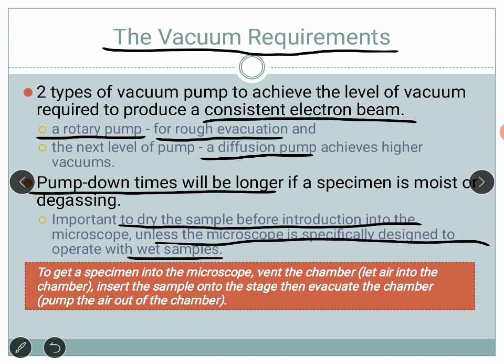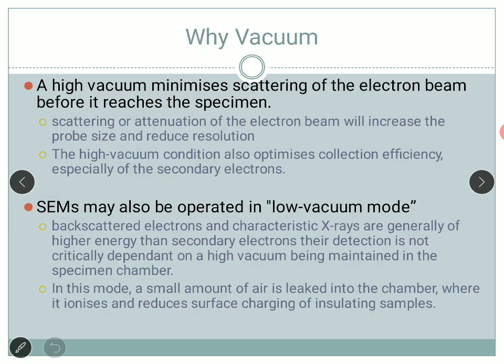The vacuum system is most of the time kept under vacuum. In order to get the specimen into the microscope we vent the chamber — we let air inside. After that we open the chamber, put the sample onto the stage, and then evacuate the chamber again before starting the experiment. The vacuum, at a high level, minimizes the scattering of the electron beam before it reaches the specimen. We want the electron to be focused and not scattered when it reaches the specimen.